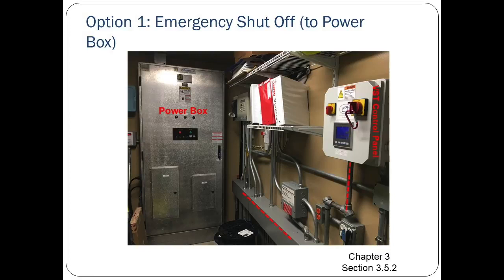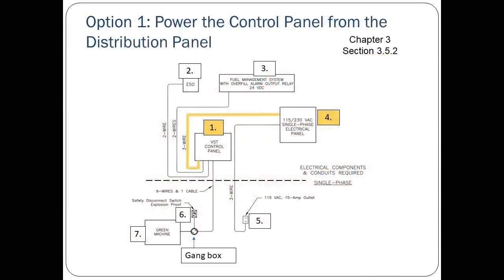Here's a picture of the inside of a data hut. Note the VST control panel on the right and the power box on the left. The red dotted line is a potential path the wires can be run along. The ESO circuit to the VST control panel must be installed for it to have power to operate the green machine. It is required that the VST control panel and in turn the green machine lose power when the emergency shutoff system is activated. Note that in Option 1, 3 power wires were pulled from the electrical panel. For Option 2, this connection is unnecessary.